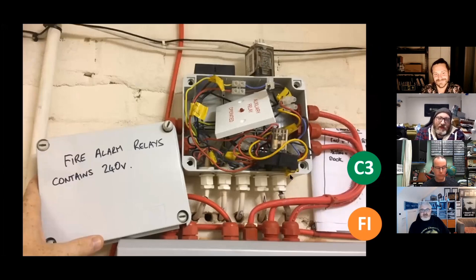So this is a visual feast. This is charming. I like this one. It's a visual feast, isn't it? It's just all over the shop. Fire alarm relays contains 240 volts. God bless you in your old school use of the 240 volt terms. Right, bottom right cable has been pulled out of the compression fitting. Yes. No protection of the cable penetrating through the...